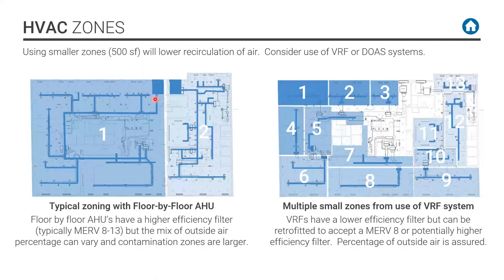So each has its advantages and disadvantages. For a floor by floor unit or even a central system, the air all gets mixed, it goes back, but the air handling units can have a much better filter. You can get a MERV 13, 14, 15, probably in the floor by floor units. That's a positive thing.